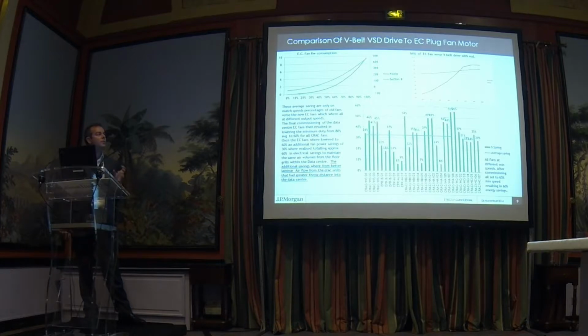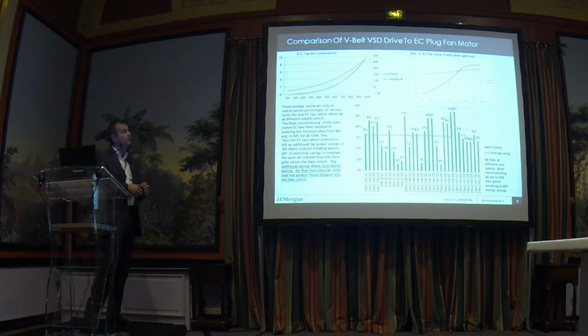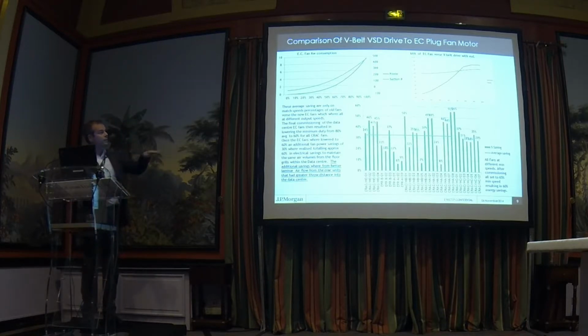when you oversize the fan and you oversize the EC electric motor, EC electrically commutated motor, there's no brushes, there's no metal, there's no induction, there's no bad power factor losses inside these motors. But once I leveled the machines off at 65%, I basically got a saving upwards of about 55, almost 60% to move the same amount of air, which is quite considerable when you look at base load and these things just running and humming 24/7.